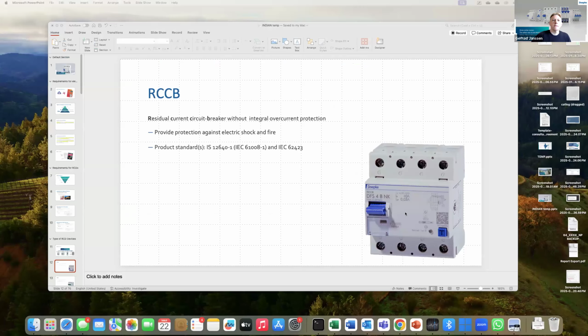Sir, there is no ELCB available in the market. If you are using an ELCB, I highly doubt it. The device you are using, hold on, I'll share my screen. Does it look like this, the device? Yes, sir. So that is an RCCB, not an ELCB. Now, the question comes, is it the right way of using it? It depends on the equipment. If you're using welding equipment and using an RCD, then it has to be a type B, because the nature of the equipment is very different. There is no limit on the amount of leakage current, and no limit on the nature of the leakage current either. So then you need a type B.